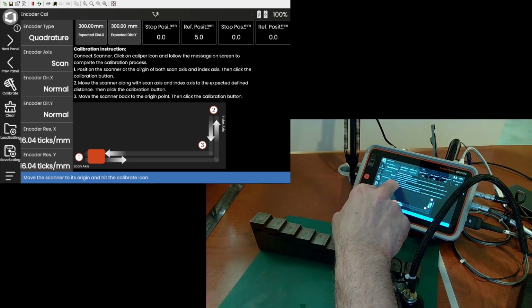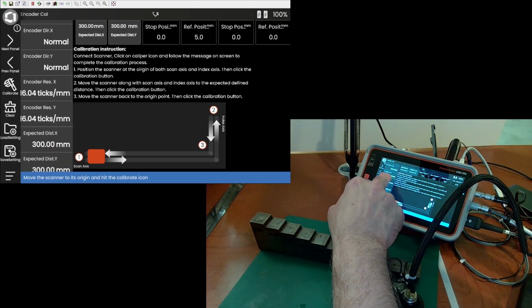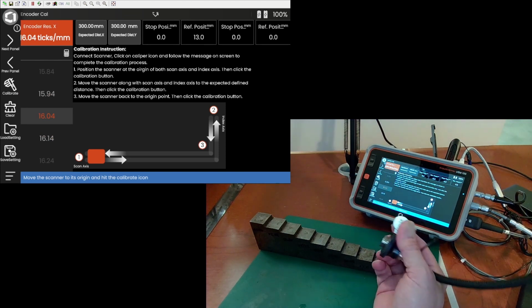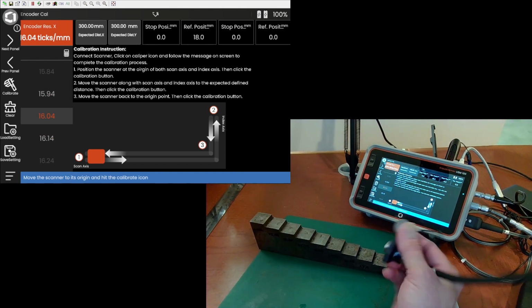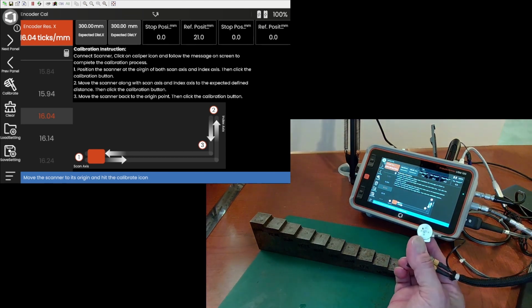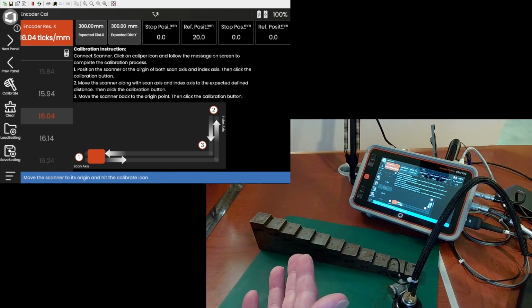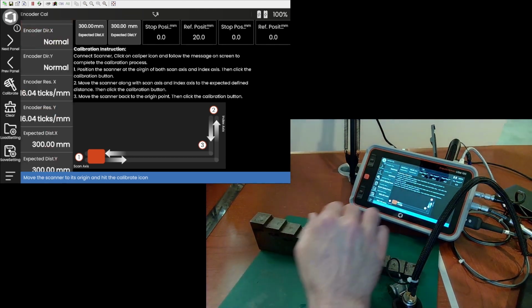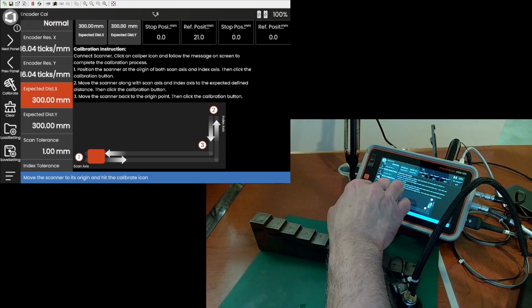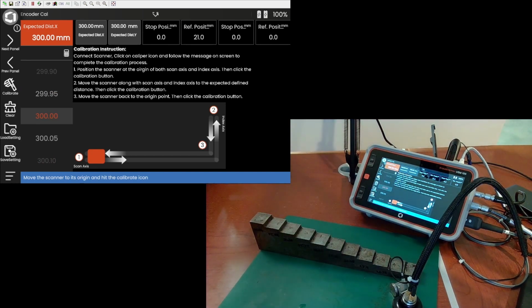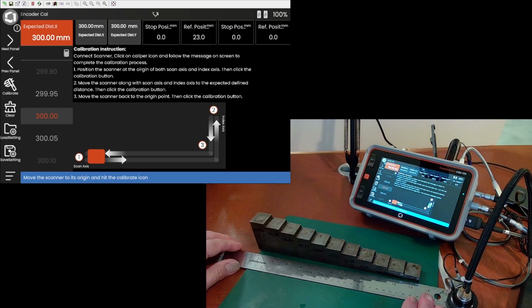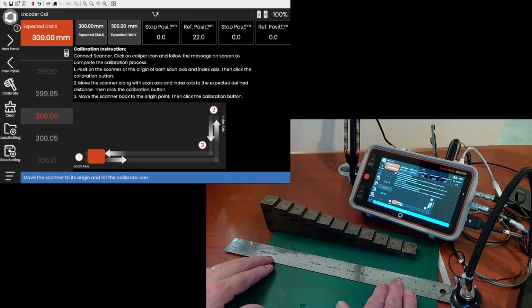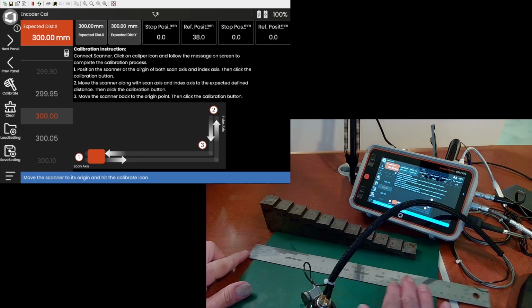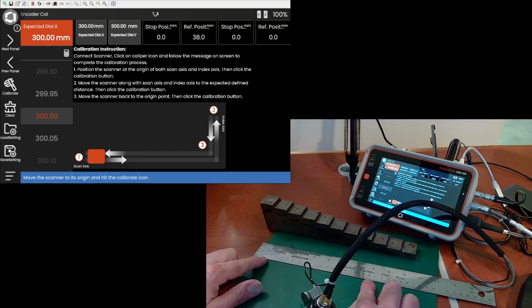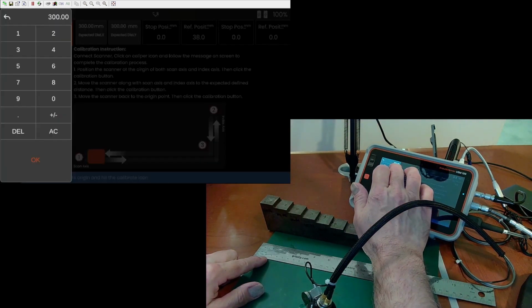We'll let the direction set as normal for now. We can ignore the Y. The default ticks per millimeter is actually roughly correct for this encoder, so we can leave that alone. If we happen to know that our encoder is, say, 20 ticks per millimeter, we can set that here as a starting point. Next thing we're going to do is tell it how far we are going to move the encoder during calibration. So I'm going to bring out a ruler, and we're going to take a look here. I'm going to use 300 millimeters as an expected distance for my encoder calibration. So we'll set this to 300.